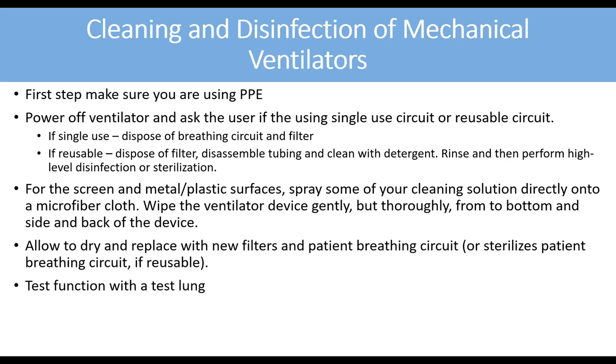Ask the user if using single use circuit or reusable circuit. If single use, dispose the breathing circuit and the filter. If reusable, dispose the filter, disassemble the duct tubing, rinse, and perform the appropriate level of disinfection or sterilization. So this is the method for the tubing, breathing circuit, and all that.